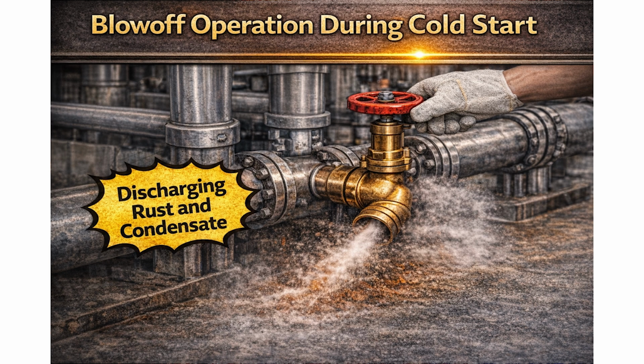Now, let us look at another condition where orifice traps do not work well. Factories that do not treat cold start as a special operating condition. At startup, everything is cold: the piping, the equipment, the internal metal surfaces. When steam is introduced at this moment, a very large amount of condensate is generated, much more than during normal operation. Normally, during startup, a bypass valve is temporarily opened. Condensate is discharged before normal operation begins. This prevents water hammer. It also prevents rust and debris from entering equipment.